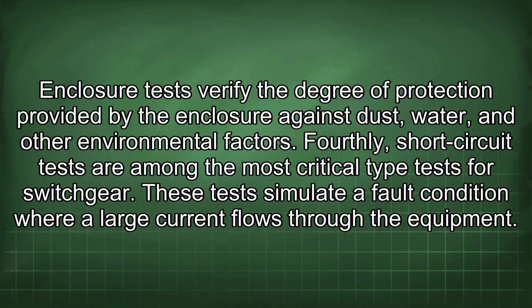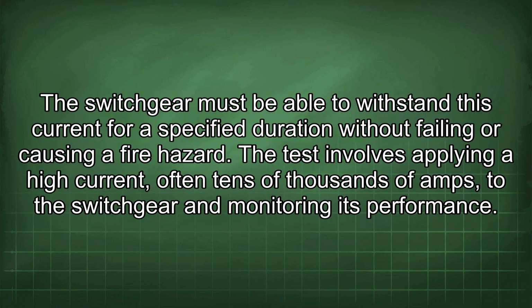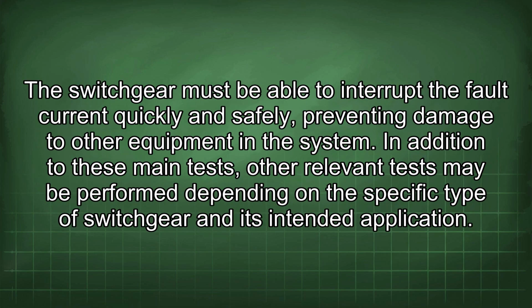Fourthly, short-circuit tests are among the most critical type tests for switchgear. These tests simulate a fault condition where a large current flows through the equipment. The switchgear must be able to withstand this current for a specified duration without failing or causing a fire hazard. The test involves applying a high current, often tens of thousands of amps, to the switchgear and monitoring its performance. The switchgear must be able to interrupt the fault current quickly and safely, preventing damage to other equipment in the system.